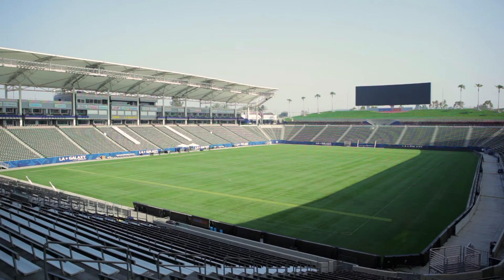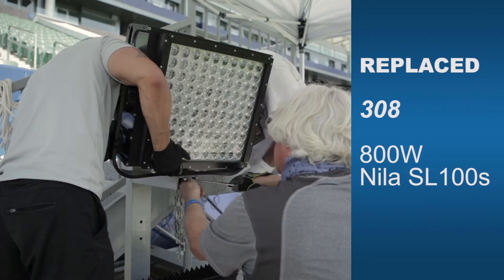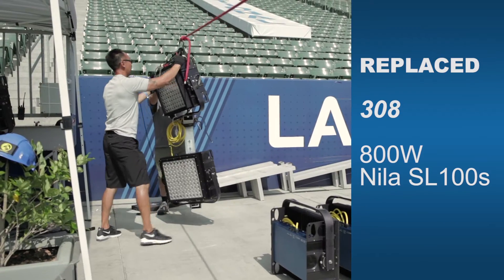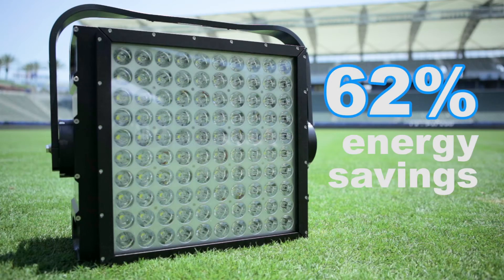We replaced 396 1500-watt metal halides with 308 800-watt Nila SL100 fixtures. That's a 62% energy savings.